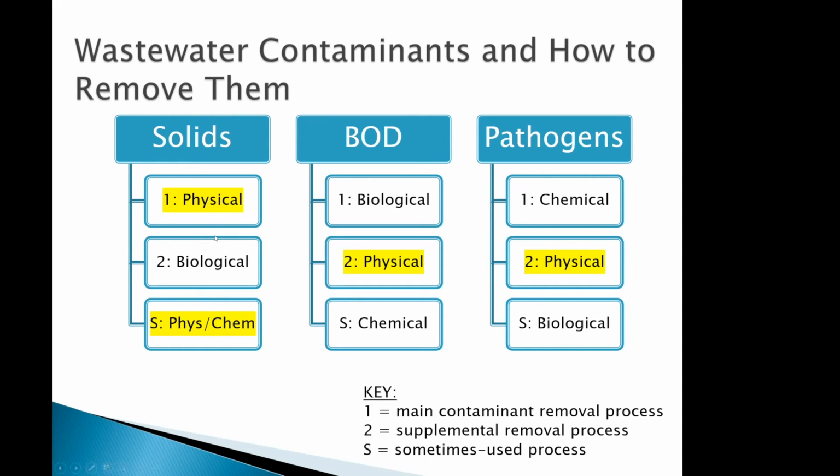So obviously, physical removal of solids is occurring, and that's the primary thing that's occurring. But what we also need to understand is that a large portion of those solids are made up of biochemical oxygen demand. So a primary clarifier is actually kind of a secondary process to remove BOD from our wastewater stream. It's not the main focused process like activated sludge that you just learned about, but it's important to remember that the primary clarifier plays a critical role in BOD removal as well.